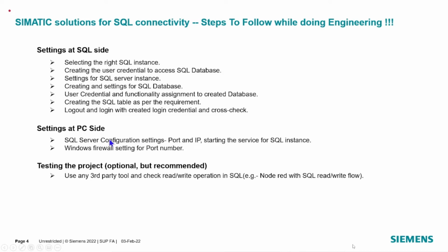With that, you are able to read and write data. Is there any difficulty or not? Once this is tested, then you are clear that everything from the SQL side is okay. You could test the operation or sequence with any third-party software. In case it is not working with the PLC, you are sure, okay, I have already tested the SQL side, so more I have to focus on the PLC side. That way you can pinpoint the issue in case there is any communication issue.